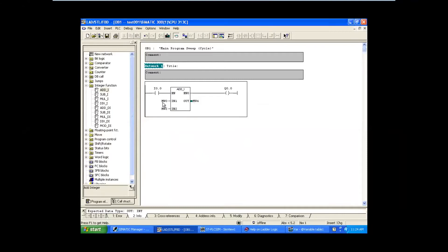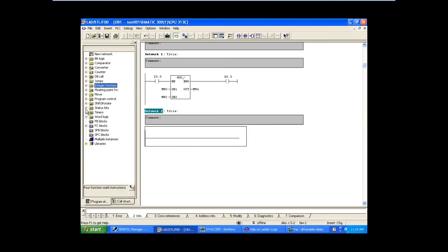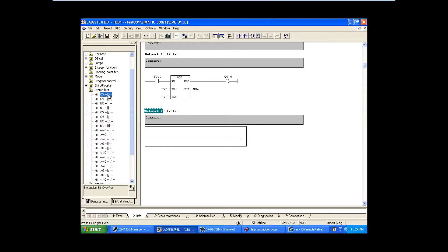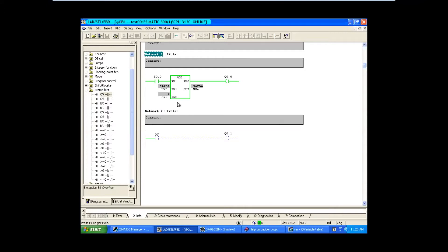Suppose if the MW4 value is beyond 32768, how do we get to know that the block is beyond the limit? In such cases we can make use of the status bit to show some indication. I am going to add one more rung and add the status bit overflow as an input contact, then connect one output. Now I have given some values stored in MW0 and MW2, and the value in MW0 is 16256, so the answer is also 16256 - this is within the limit.